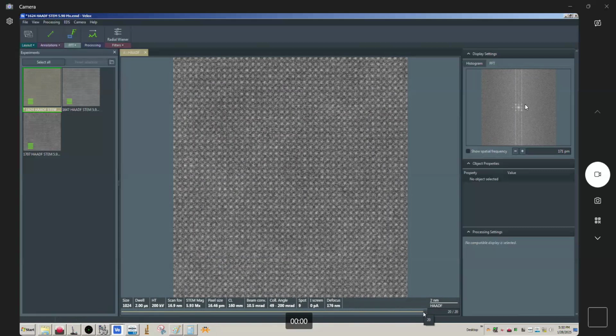So that's another problem that I've noticed, that when the drift is not predictable or constant or stable, this also tends to have issues, okay? And unfortunately in the Talos, we're in the room with the microscope, and that's probably the biggest reason why we see this kind of instability, even though I think the room met all the specs when the microscope was installed.